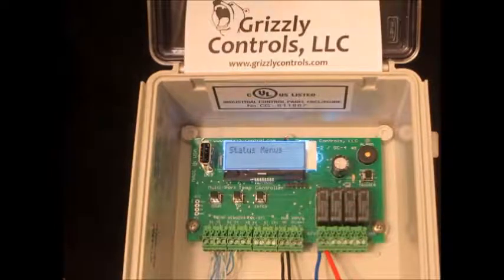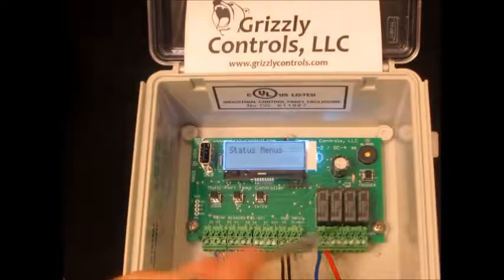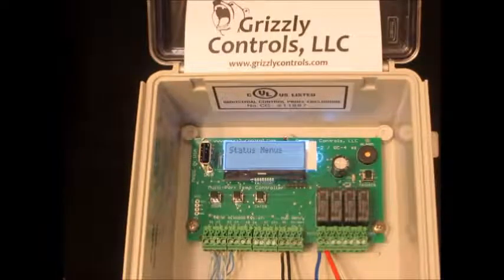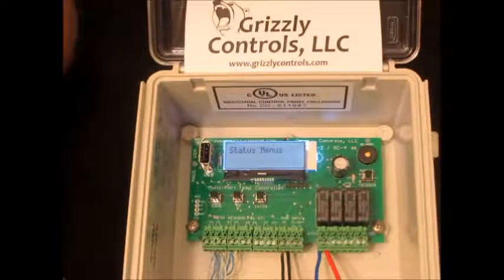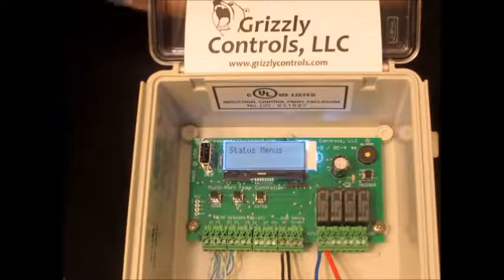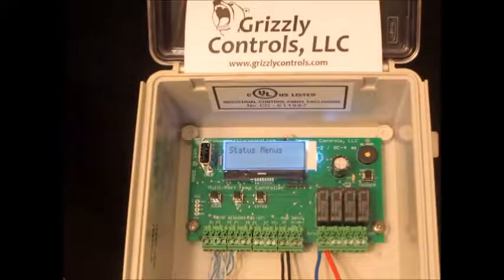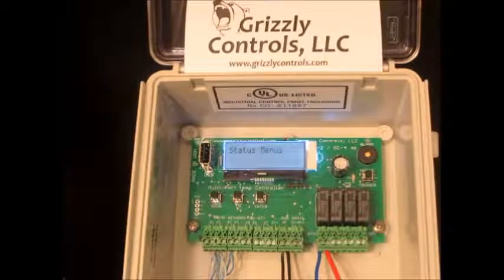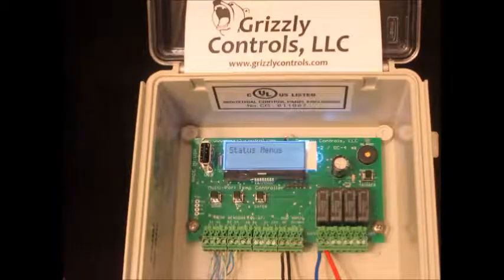There are 4 relay outputs on this unit. They can be configured and controlled with any of the 8 onboard control rules that you configure. Each one can switch up to 5 amp loads, DC or AC. There's a manual trigger button over here on the right side. You can use this to configure and enable a one-shot timer. You can use that to override one of the outputs and control the relay, so you can push that button, and if it's configured for relay 1, it'll turn that relay on for the one-shot timer duration. You can use that for restarting a wood boiler, for example, things like that.